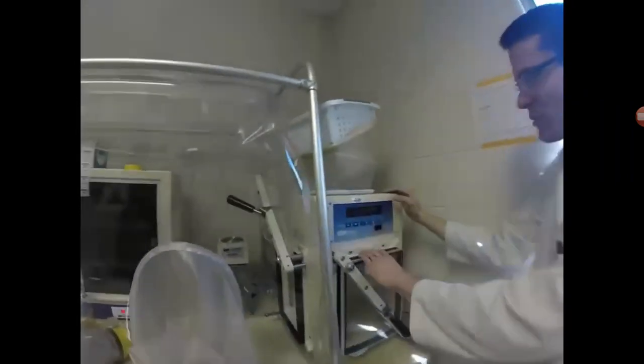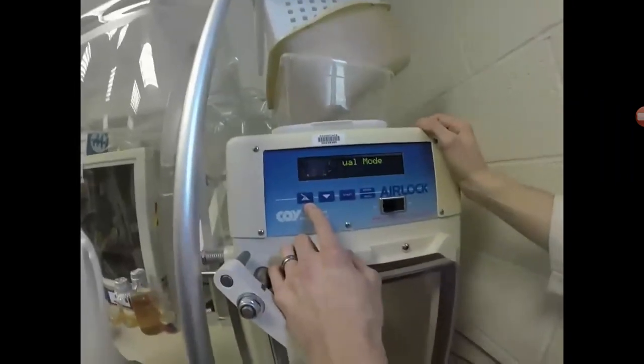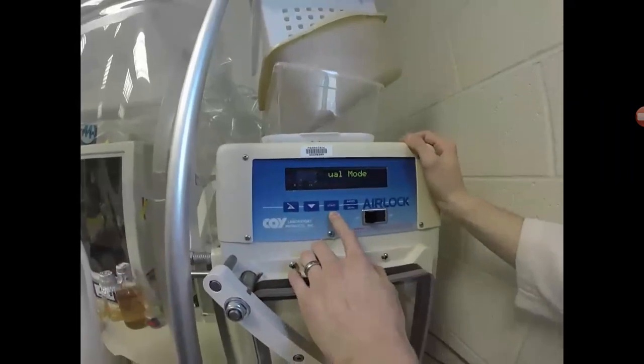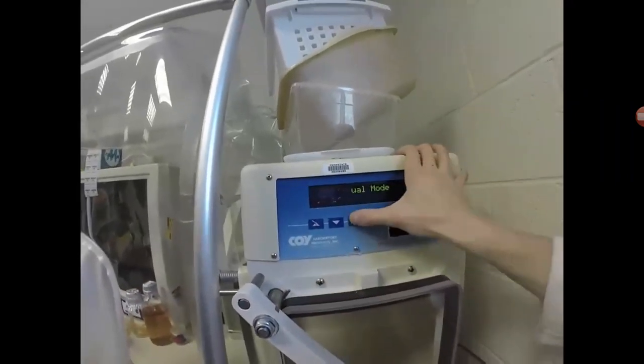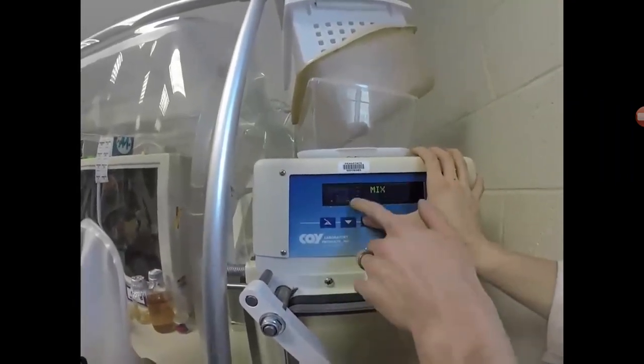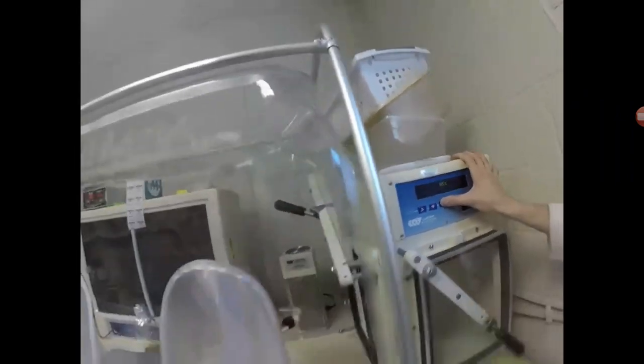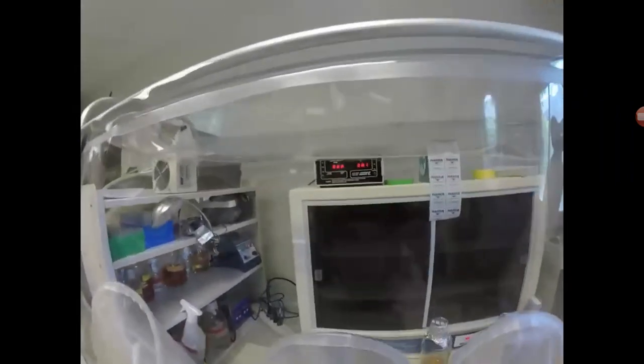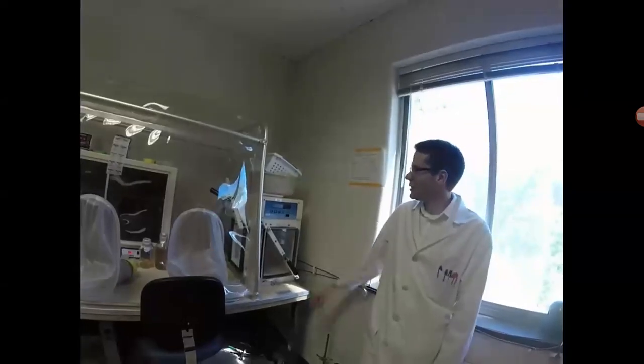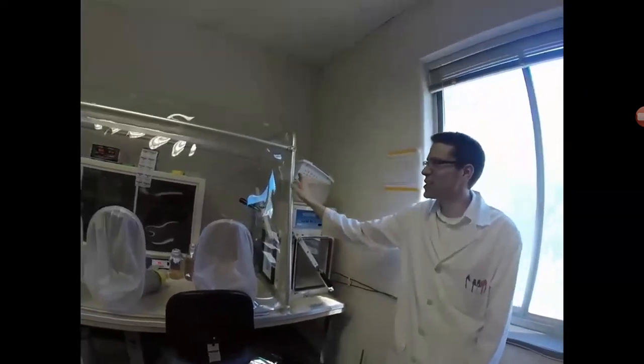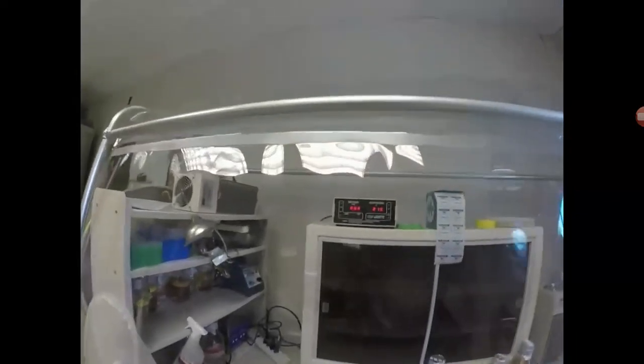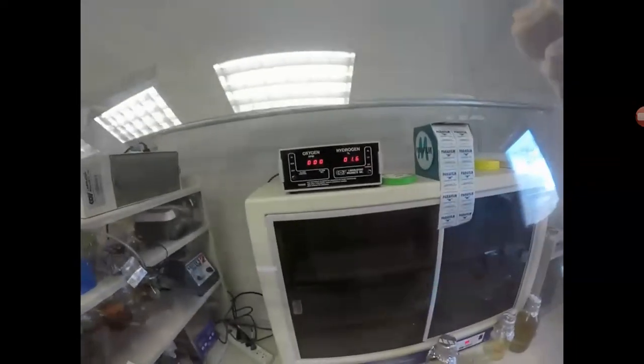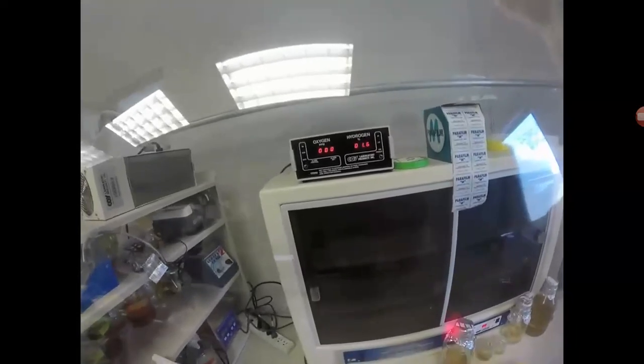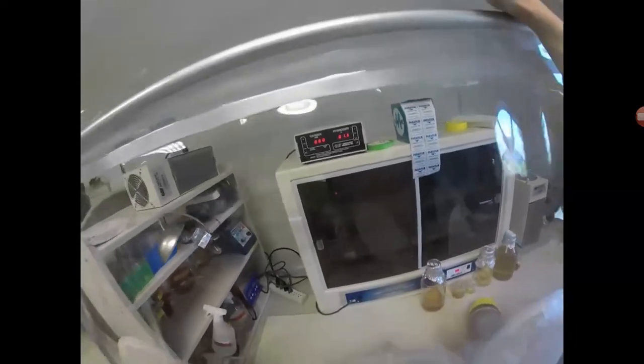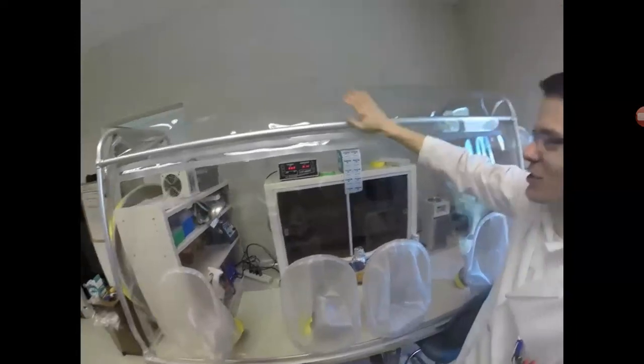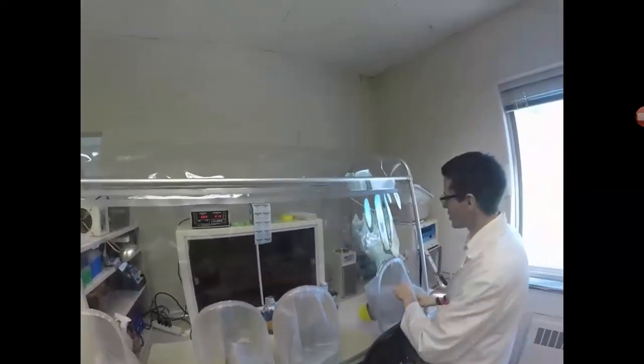Okay, so now that we've got a vacuum pulled on, we can fill it back up with mixed gas. If you recall, the up button is for the vacuum, the down button is for the purge gas, and the start button is for the mixed gas. So we're going to just push start, and as you can see what it's doing, it just says gas mix. It's simply going to pump the chamber full of gas. Okay, so we just finished filling the chamber with the gas mix. As you can see, it's now puffed back up, and we are at a hydrogen concentration of 1.6%, which is sufficient for our needs at this point. So now it's fine. We can just leave it. Before we leave it, though, we should shut this door.